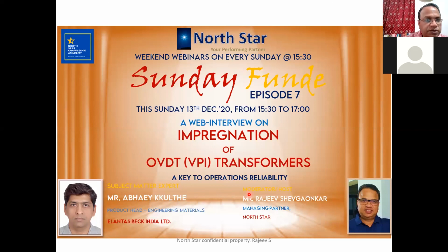So now I'm taking the question from the chat box, that is, what is the effect of power factor on transformer life? That is, the megawatt load is the same, but the power factor is increased to 0.98 from 0.9. So, very right question, sir, that as you are increasing the power factor, basically what you are doing is you are using the transformer close to its MVA rating. So if you have unity power factor, then your MVA will become equal to your megawatt.